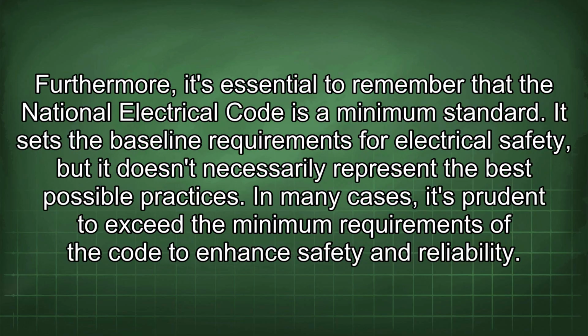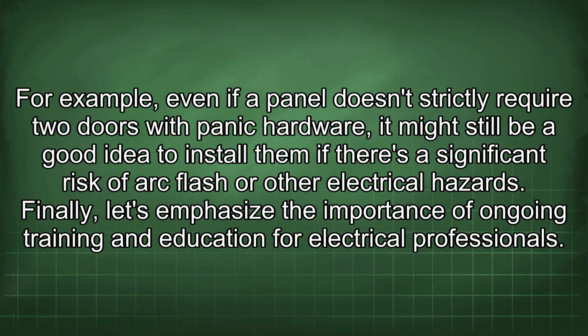Furthermore, it's essential to remember that the National Electrical Code is a minimum standard. It sets the baseline requirements for electrical safety, but it doesn't necessarily represent the best possible practices. In many cases, it's prudent to exceed the minimum requirements of the code to enhance safety and reliability. For example, even if a panel doesn't strictly require 2 doors with panic hardware, it might still be a good idea to install them if there's a significant risk of arc flash or other electrical hazards.